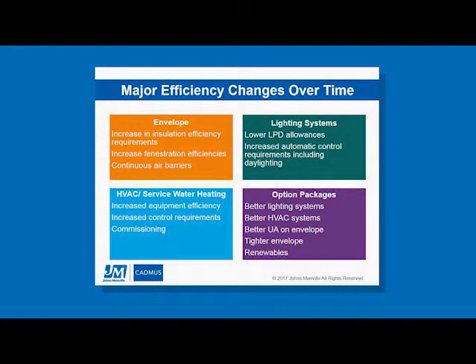It's important to note that all parts of the building systems, energy-using systems, actually contributed to these efficiency gains. Obviously, envelope is a major player on this, and over time there have been significant increases in insulation requirements, things like requiring continuous insulation on metal and wood frame wall systems, better metal building insulation, but really focusing on increasing the insulation levels in all parts of the building, more slab edge insulation, for example. There's also been increased fenestration efficiencies because obviously glazing plays a major role in building energy efficiency depending on how much glass you have.